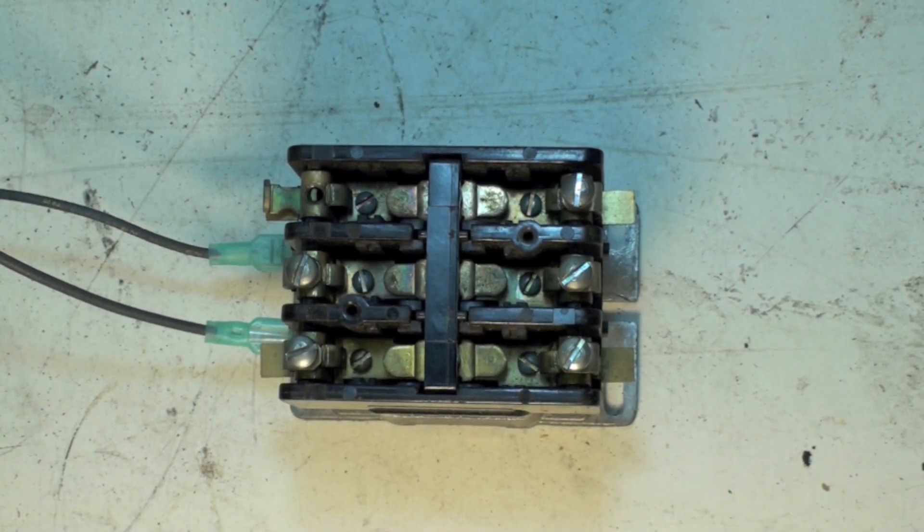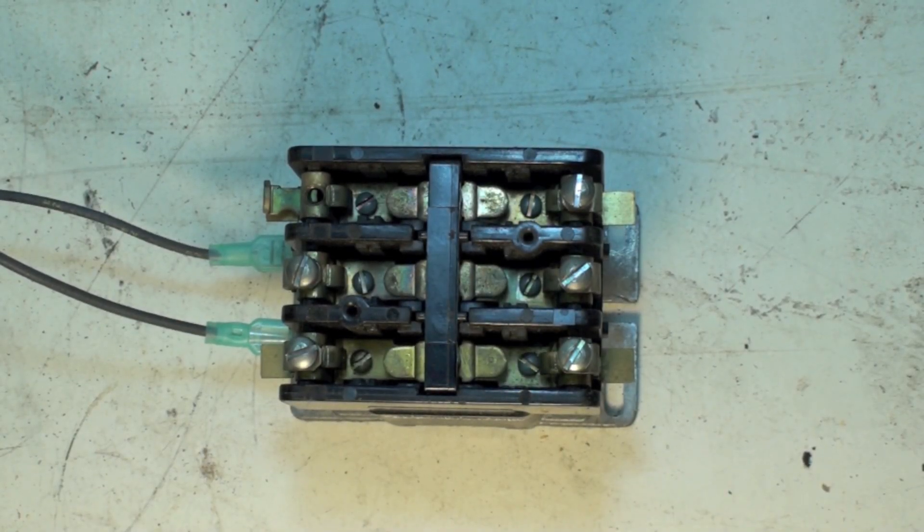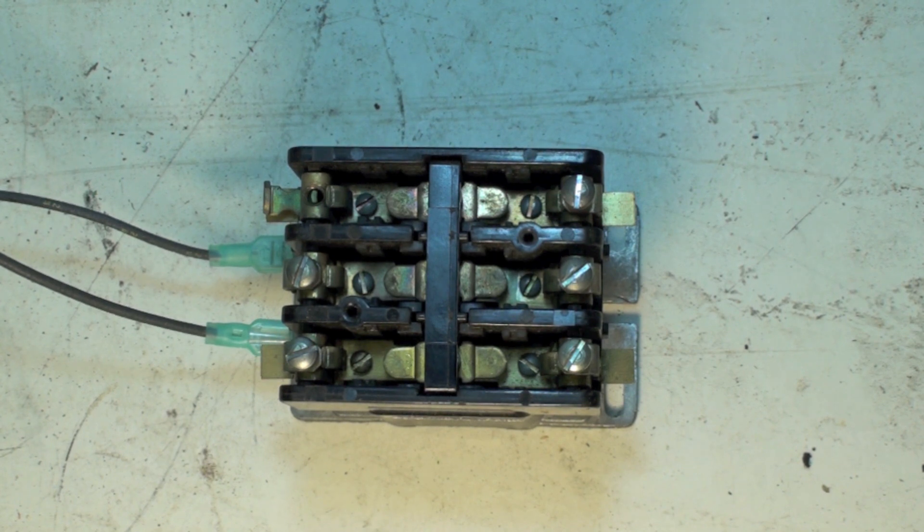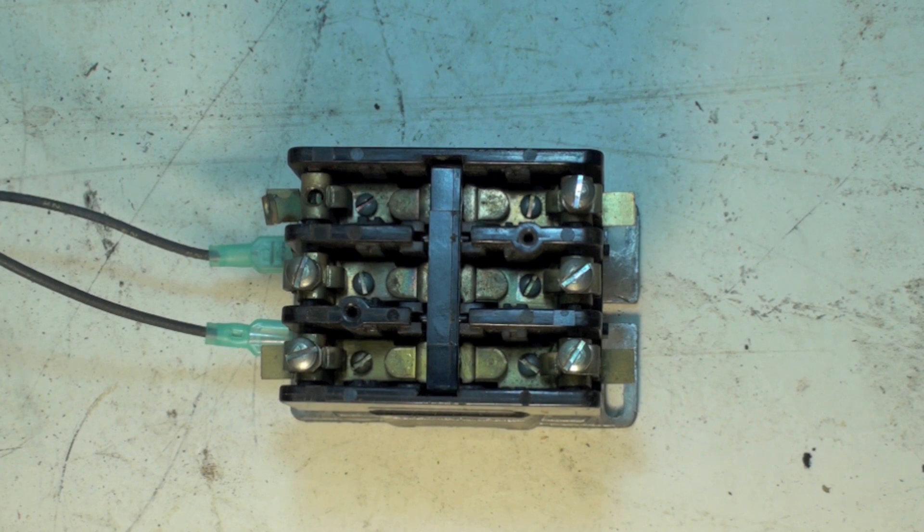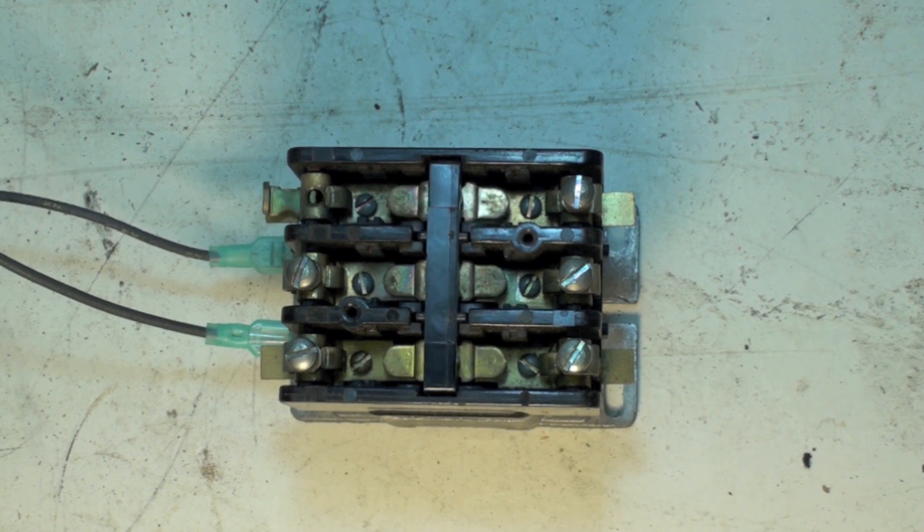Okay, when the contactor makes, it should make solidly. It should make a bit of a noise when it does. I can see that thing came down very quickly. All three of them came down.